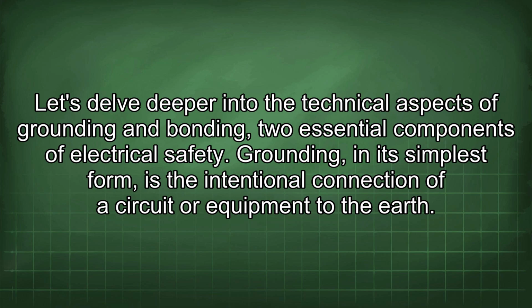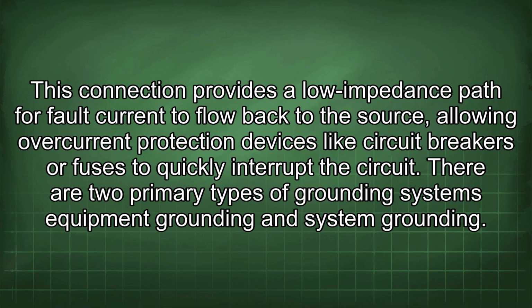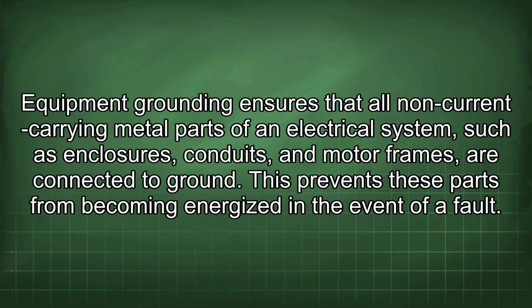Let's delve deeper into the technical aspects of grounding and bonding, two essential components of electrical safety. Grounding, in its simplest form, is the intentional connection of a circuit or equipment to the earth. This connection provides a low impedance path for fault current to flow back to the source, allowing overcurrent protection devices like circuit breakers or fuses to quickly interrupt the circuit. There are two primary types of grounding systems: equipment grounding and system grounding. Equipment grounding ensures that all non-current carrying metal parts of an electrical system, such as enclosures, conduits, and motor frames, are connected to ground. This prevents these parts from becoming energized in the event of a fault.